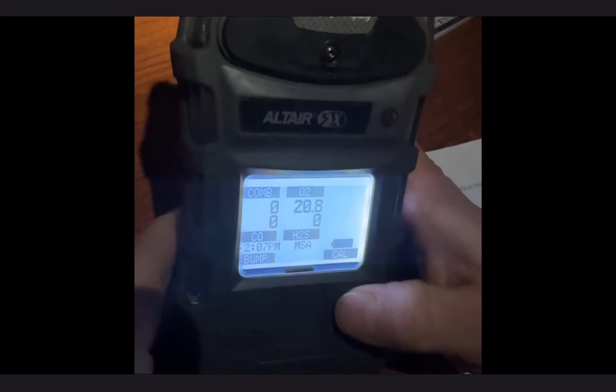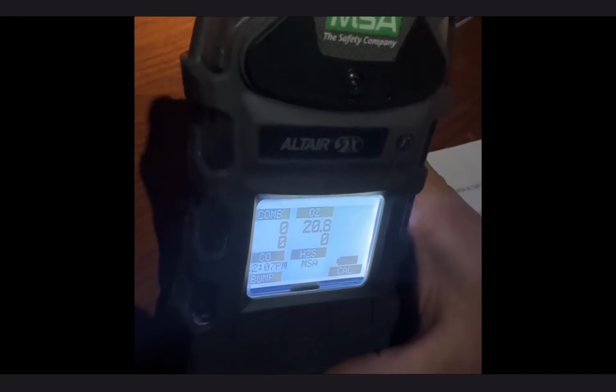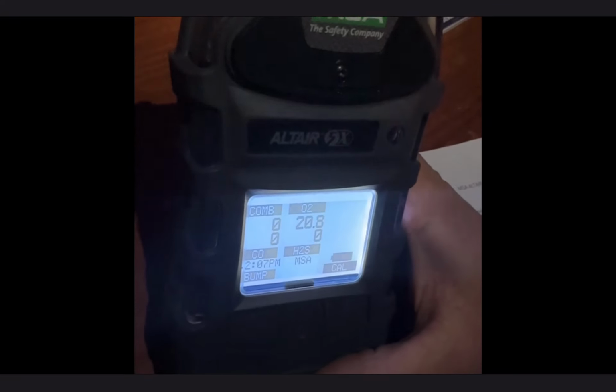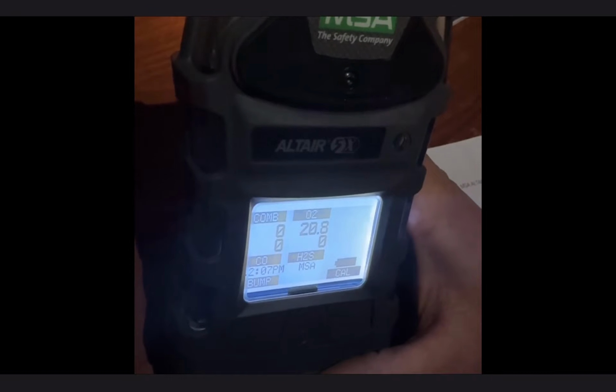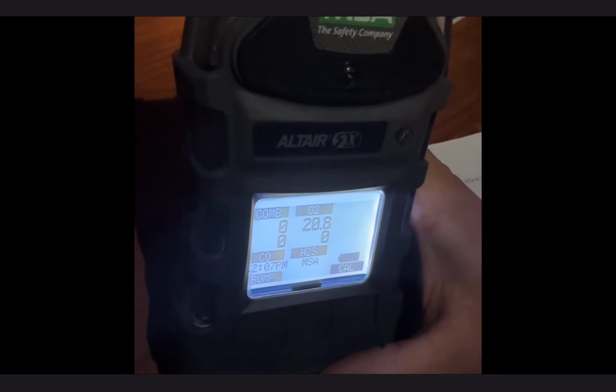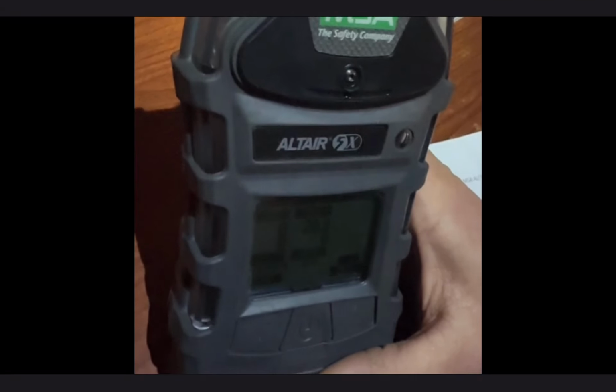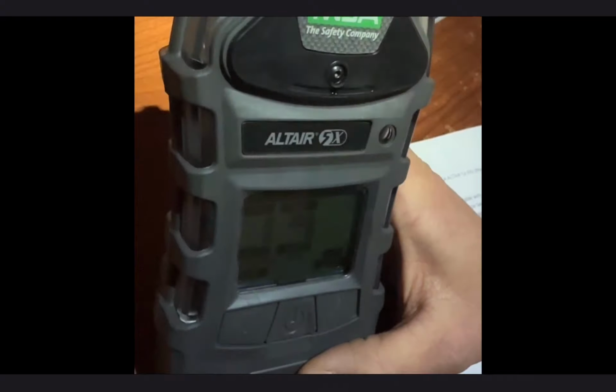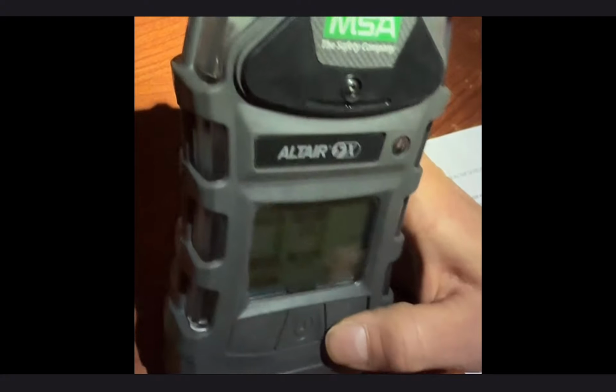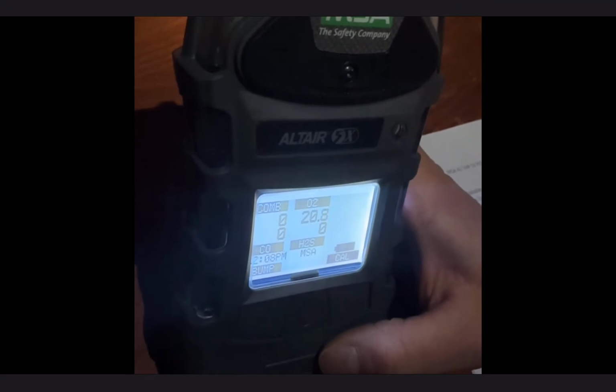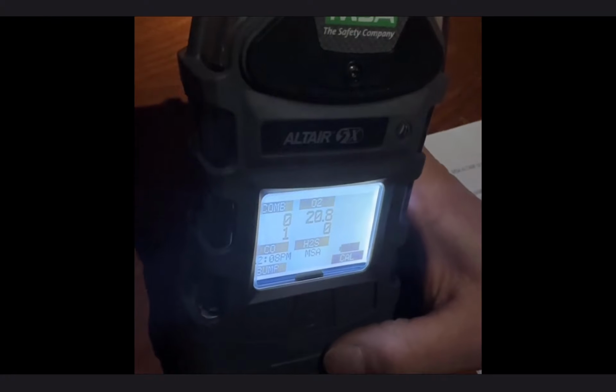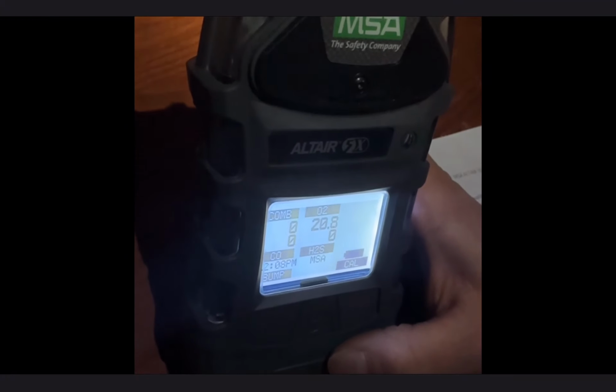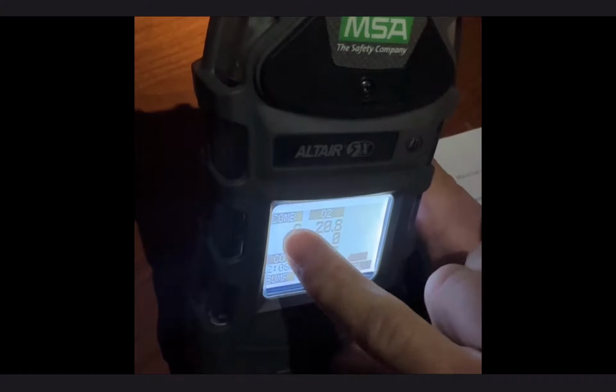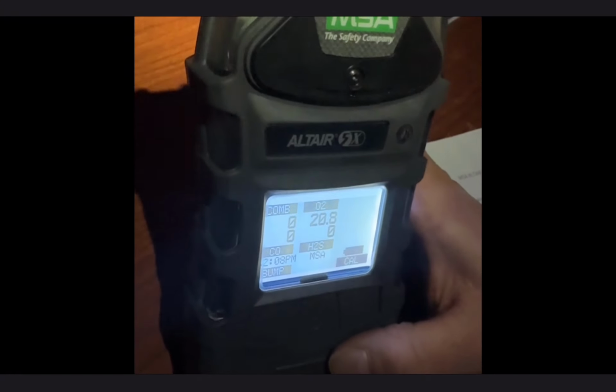You see a bump test and a calibration. We often confuse bump testing and calibrating, so I want to get the record straight that bump testing is more of an industry thing. It's just testing to make sure that the monitor detects the 4 things it's monitoring for. Is it detecting O2? Is it detecting LEL, CO, H2S? We calibrate because we don't work in the industry setting and we do it once a week. And the calibration is making sure not only does it detect those 4 sensors, but does it detect it within range so that when you're monitoring and measuring, you're actually getting an appropriate reading of what's on here within range.